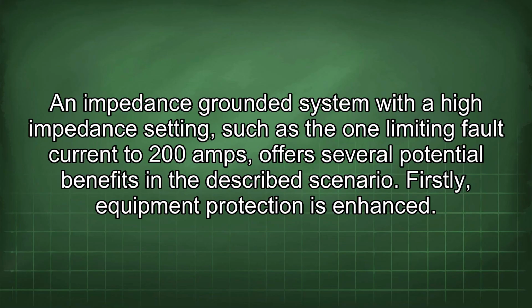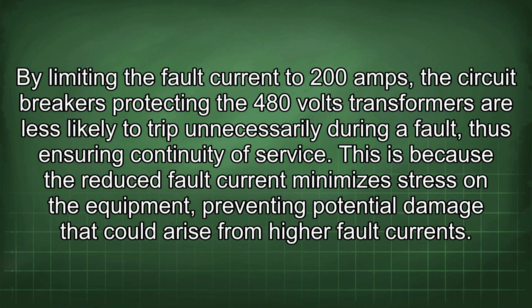An impedance-grounded system with a high impedance setting, such as the one limiting fault current to 200 amps, offers several potential benefits in the described scenario. Firstly, equipment protection is enhanced. By limiting the fault current to 200 amps, the circuit breakers protecting the 480 volts transformers are less likely to trip unnecessarily during a fault, thus ensuring continuity of service.